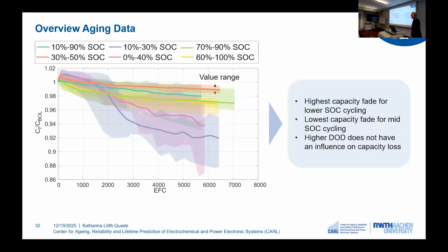And here we can see we have the lowest capacity fade for these conditions. And we can also see that the higher depth of discharge does not have an influence on our capacity loss. We can see, for example, that this purple condition, 10% to 30% SOC, has higher capacity fade, even though the depth of discharge is lower compared to the condition that you can see here in pink.